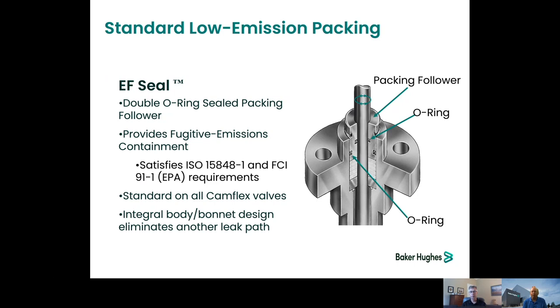In a rotary design, the shaft rotates in place, so you're not pulling any contaminants into the packing system. The rotating motion is a lower friction to the packing compared to a sliding stem motion, so there's much less packing wear in general.